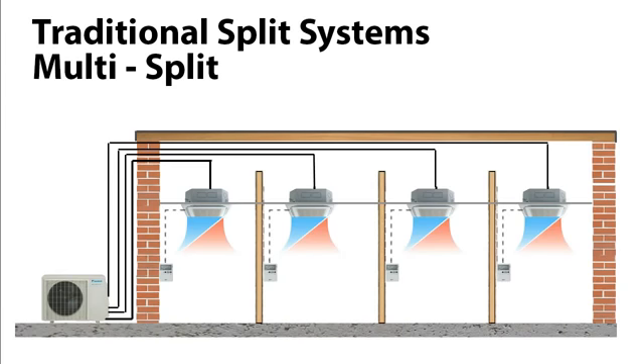Now the next advance from that was the multi-split unit, as you can see here on the screen. And this did allow multiple zones to be fed from one condenser unit, although there's a lot of pipework that has to be installed, so each zone is individually piped. So it's quite a lot more effort to install, and these systems are usually way oversized and they do not provide very good or very close control. VRF units, on the other hand, can supply multiple zones, and we're going to see how the different versions can also provide different thermal comforts and also how they save a lot of energy in the buildings.